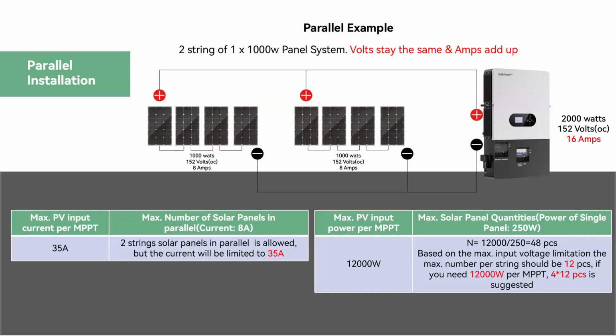Now let's look at how many strings we can parallel. As we mentioned, the maximum PV input current is 35 amperes per MPPT. So 35 divided by 8 means we can parallel 4 strings per MPPT. Taking the maximum power into consideration, 12 kilowatts divided by 250 watts means 48 pieces. So in this case, we can connect 4 strings of 12 panels each, suggested per MPPT.